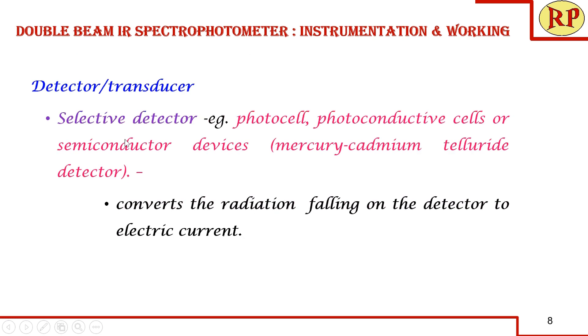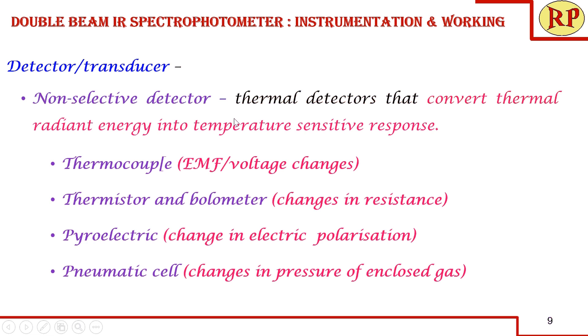There are two types of detectors. Selective detectors, similar to those used in UV spectrophotometry and colorimetric analysis — such as photocells, photoconductive cells, or semiconductor devices — convert the radiation falling on them into electric current proportional to the intensity of the transmitted light. Non-selective detectors, commonly called thermal detectors, convert thermal radiant energy into a temperature-sensitive response. Depending on the detector type: a thermocouple changes in EMF or voltage; a thermistor or bolometer changes in resistance; a pyroelectric detector changes in electric polarization; and a pneumatic cell changes in pressure of the enclosed gas.